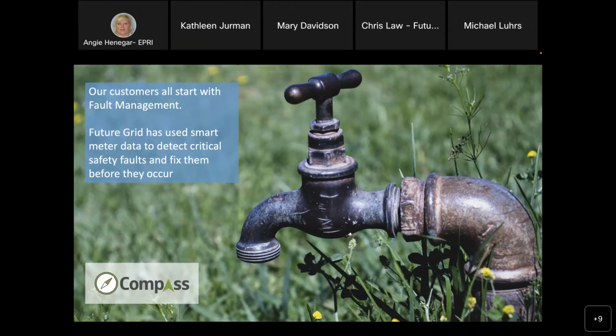I've got a tap here because in a network environment like Australia's, the configuration is such that we have a neutral at the customer premise that tends to be connected and earthed to metal pipes in the ground, often near water pipes that used to be metal. The most common fault, and the first thing every customer does with our solution, is detect safety faults where that earth has deteriorated. They call them neutral earth faults, loss of neutral, or broken neutrals, where the current can run back through and liven up the metal pipes, giving you an electric shock on your taps or gutters or anything metal that's earthed.